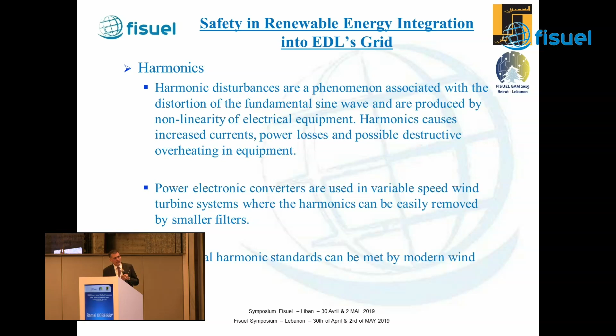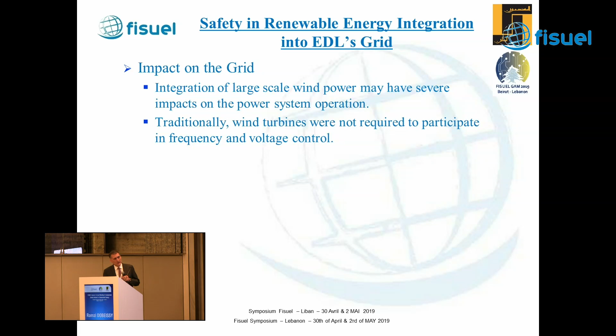The impact on the grid. Integration of large-scale wind farms may have severe impacts on power system operation. Traditionally, wind turbines were not required to participate in frequency and voltage control. Some grid codes have been defined to specify the steady and dynamic requirements that wind turbines must meet in order to be connected to the grid, like the capability of contributing to frequency and voltage control by continuous modulation of active and reactive power supplied to the transmission system, and the power regulation rate that the wind farm must provide.